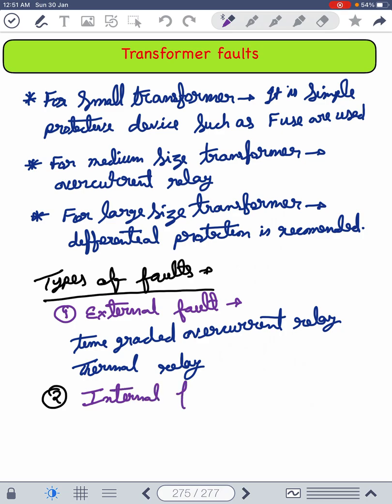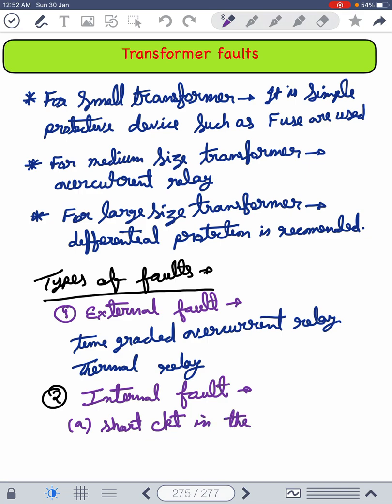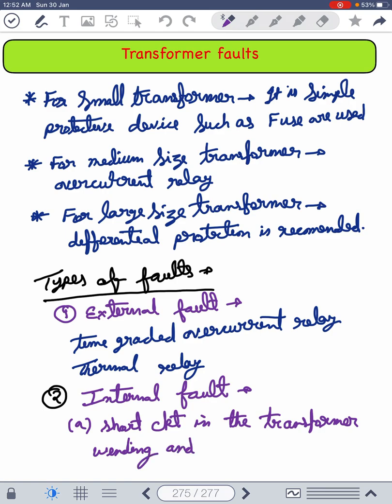The primary protection of a transformer is meant for internal faults. Internal faults are of two types. The first is short circuit faults in the transformer winding and connections. These faults are detectable at the winding terminals by unbalances in voltage or currents, and include LG, LL, and inter-turn faults on HV and LV windings.